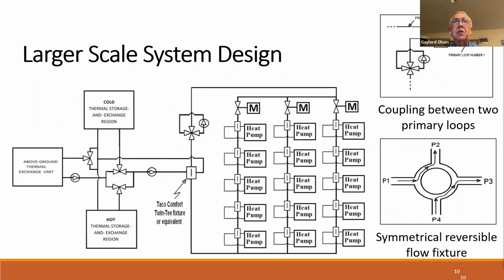Now, if you have, let's say, there's a primary loop which has that 4-way reversing valve right above the Taco Comfort Twin T fixture. The 4-way reversing valve and its associated pump provide the flow for the primary loop. With the reversing valve, we can reverse that flow direction periodically. If we could not reverse that direction and we had the flow in the primary loop always clockwise, then the top 3 heat pumps in this array would always have the best performance. They would have the highest COP and the highest thermal capacity. The bottom 3 heat pumps would always have the worst COP and the worst thermal capacity.